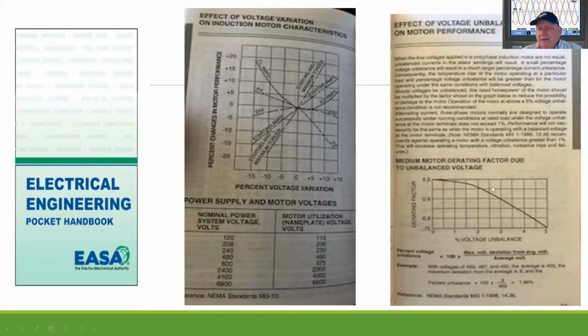The issue is that many, many times today you'll see as much as a 5% deviation in power voltages between A, B, and C. So what ends up happening is you're supposed to derate that capacity to 75%. So with a 100 horsepower motor, all of a sudden you can only really pull 75 horsepower off of it successfully without motor failure. It goes into what the nominal voltages are, what the nameplate is, and the characteristics of over voltage and under voltage. This book is a very useful tool, but I don't think a lot of people are even aware of it.